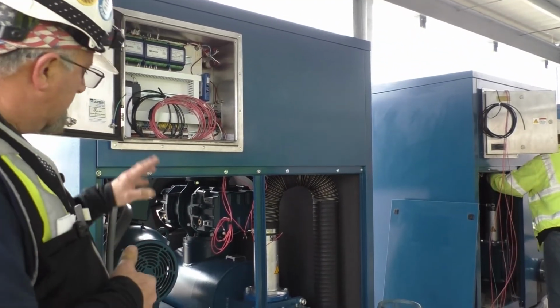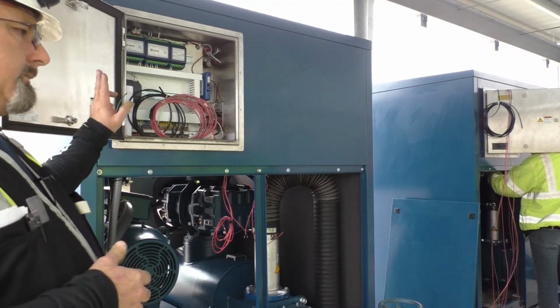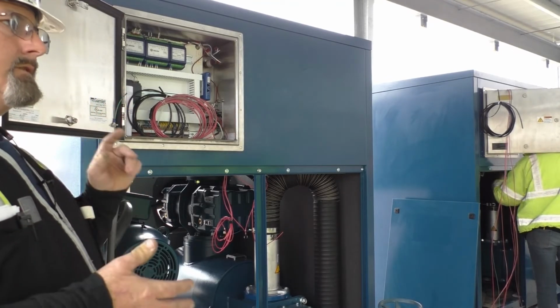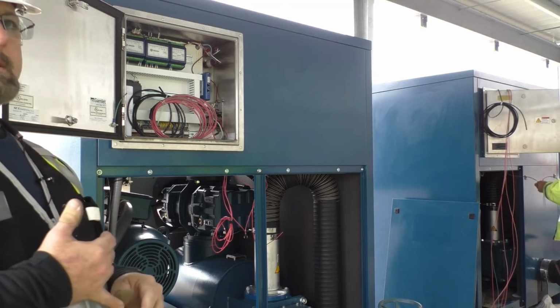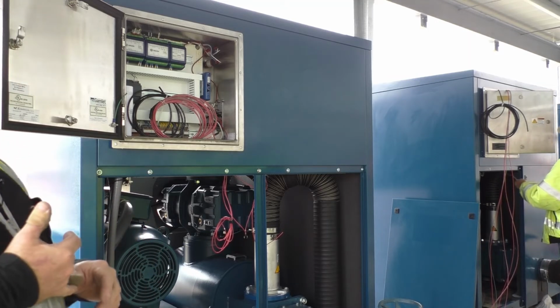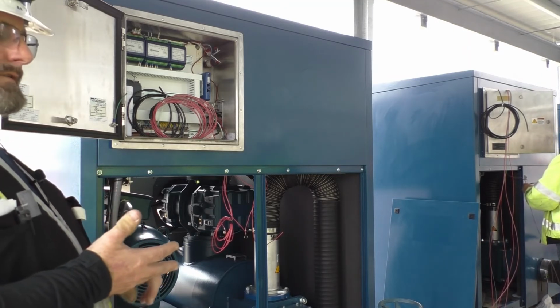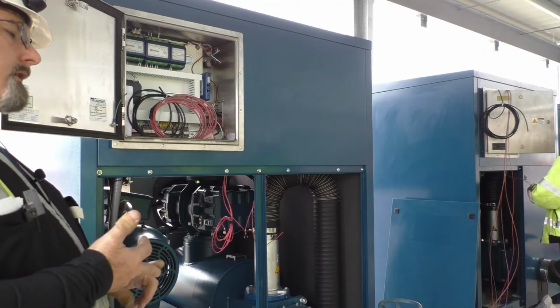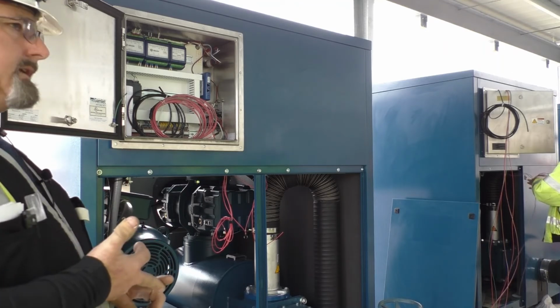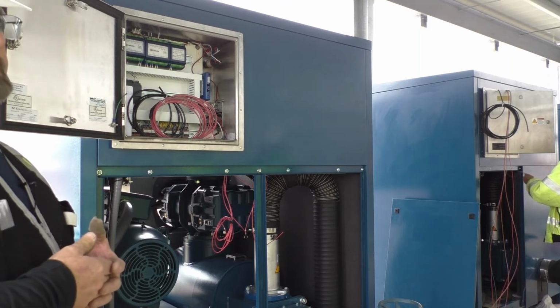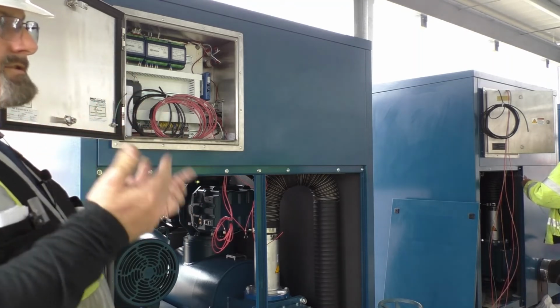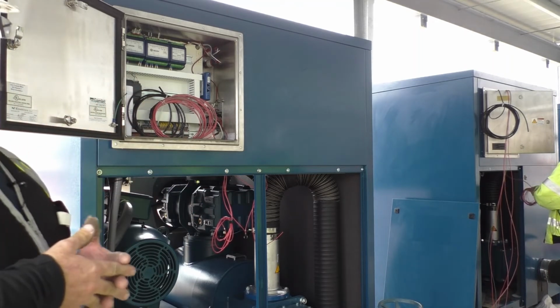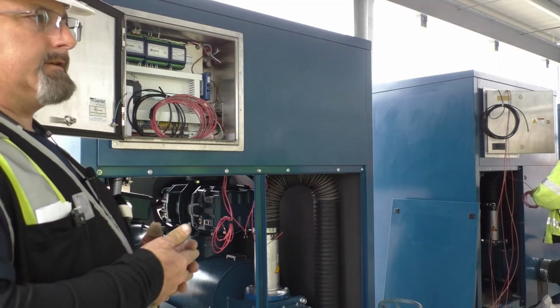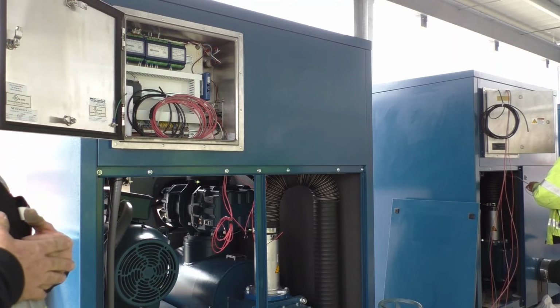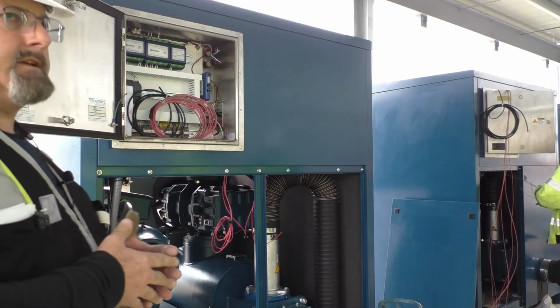Motor maintenance for these is pre-programmed into the service counters. 12,000 hours was the greasing interval that was listed on the data plate, along with the quantity of grease. The type is Mobil Polyrex EM. It's electric motor grease. So I'm sure y'all are probably using it on just about every new motor you have out here, because Polyrex or Unirex EM is becoming pretty much the standard for electric motors.